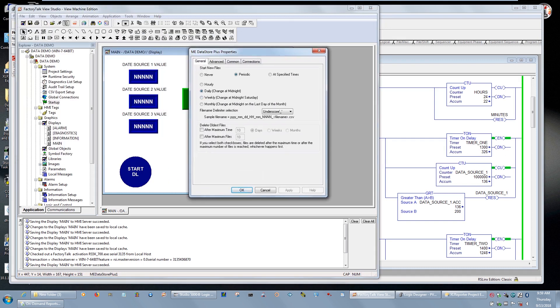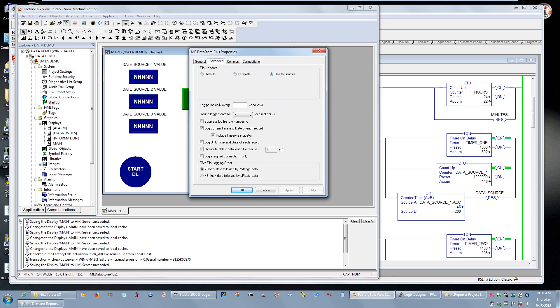When you open up the object, I always like to start a new file each day — it will create a new CSV file daily, and that's pretty much all we do in that tab. Then I always like to select Use Tag Names, which means the columns across the CSV file will have the actual tag names displayed — so if you had time, temperature settings, and other values you want to log, those columns will make sense to you. Down at the bottom, it says Log Every One Second. You could make it longer, but not shorter. This is an HMI, so keep in mind you really want logging expectations to be reasonable — one second is usually fast enough for measuring temperatures or pressure points.